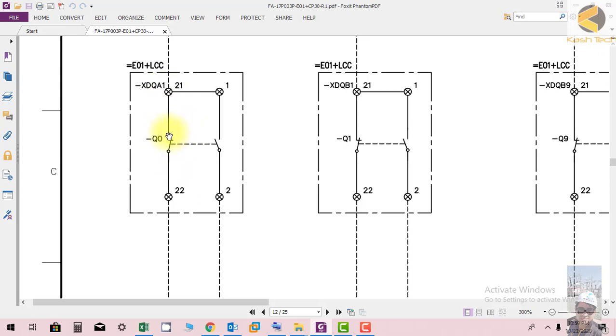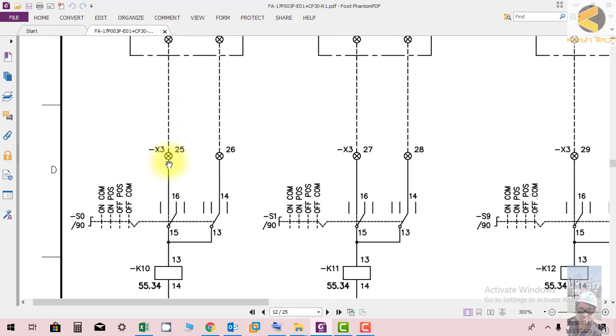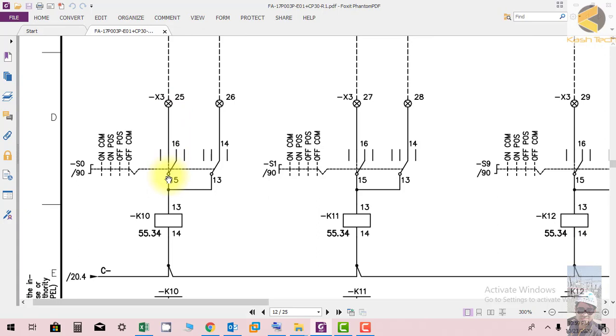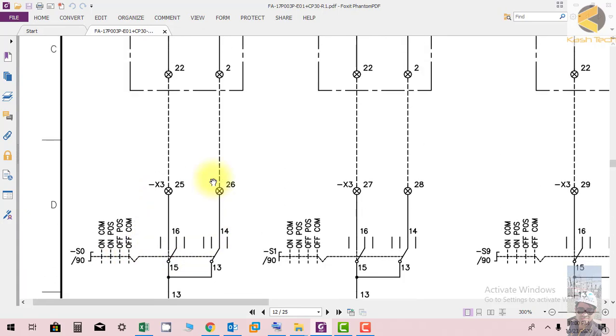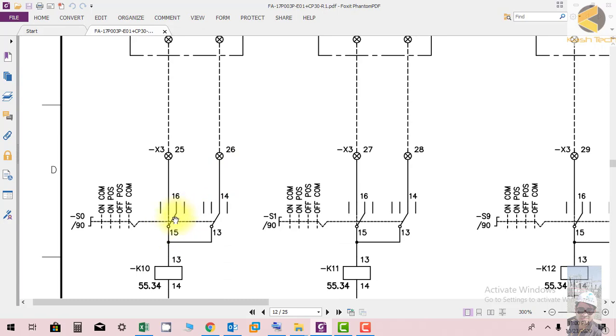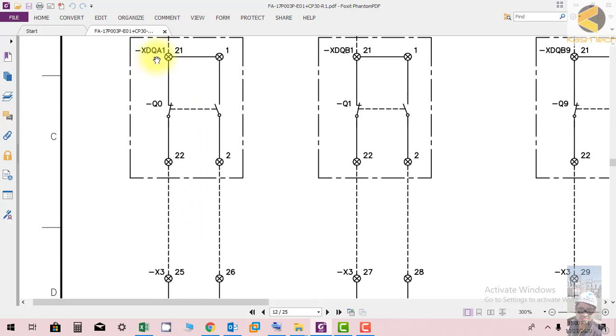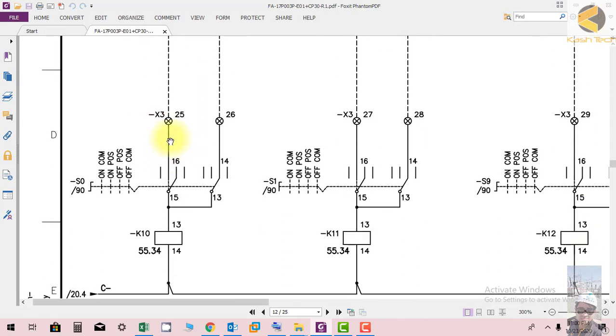The positive control supply is going from X3-10 coming to LCC. This is the normally closed contact of the breaker and this is the normally open contact of the breaker. At present in the drawing the breaker is shown in off position. The supply comes through to the selector or discrepancy switch. If the switch is in off position, supply comes from XDQA1, 21 to 22 then X3-25, supply is disconnected, and K10 will not energize.